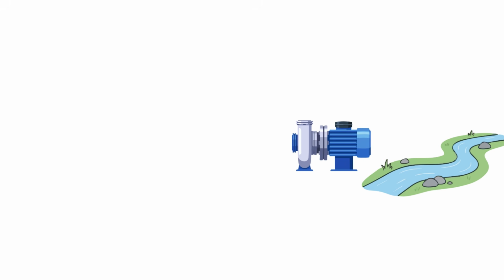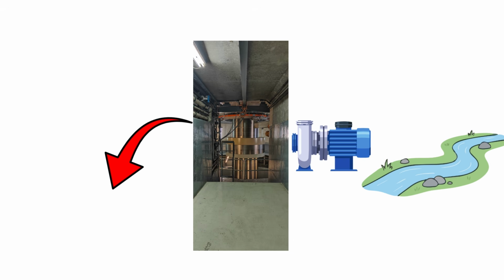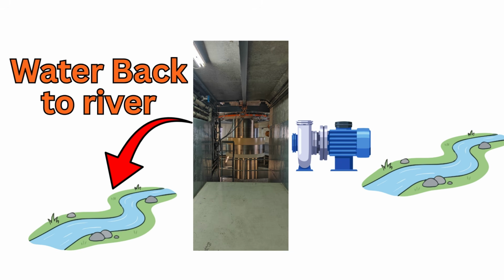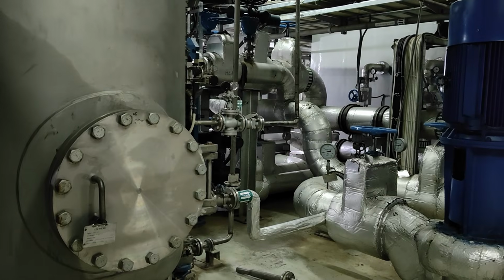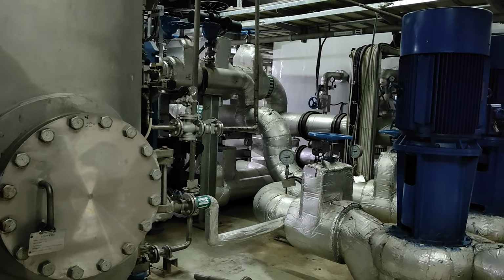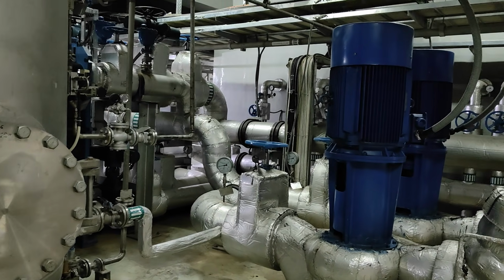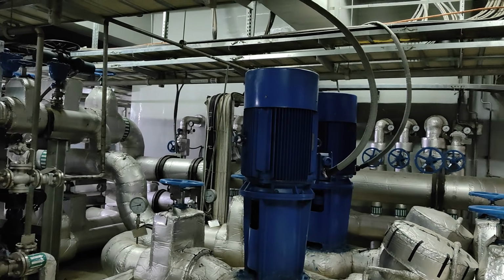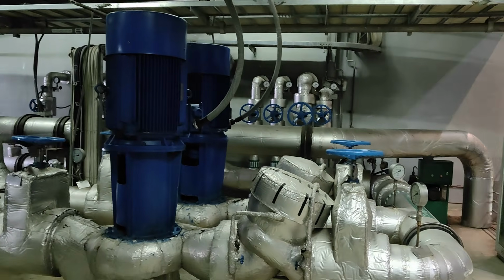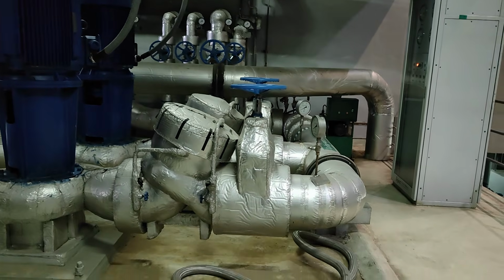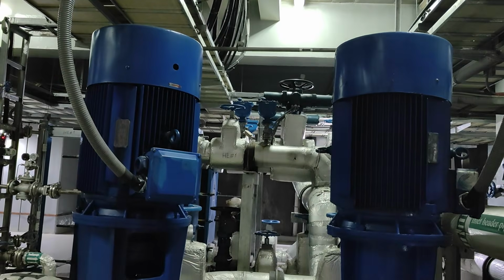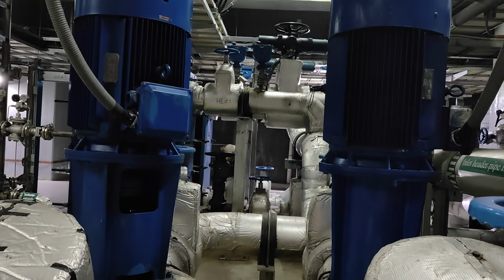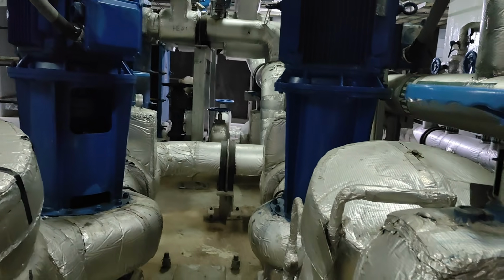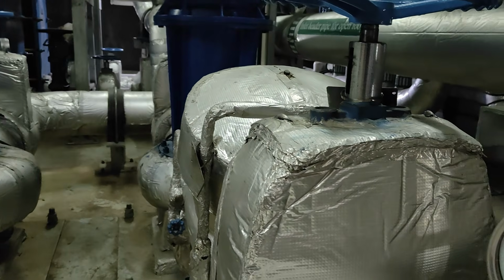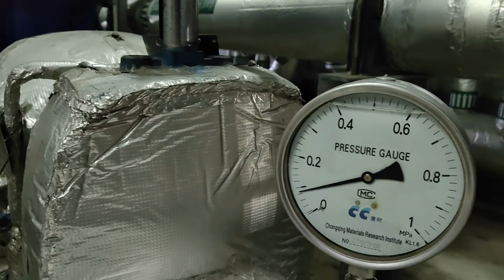Okay, now at first, using river water for cooling sounds simple. Just pump cold river water into the machine, problem solved. Except there is one massive problem. River water is dirty. It contains sand, silt, mud, stones, biological particles, floating debris, and if that dirty water enters sensitive equipment, it can destroy the entire cooling system. It would choke narrow cooling passages, damage pumps, block heat exchangers, and contaminate bearing coolers.